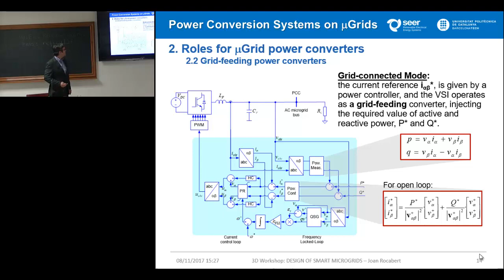Later we get the grid forming ones. The grid forming converters are voltage control systems that impose a frequency and an amplitude, and from that frequency and amplitude generate a sinusoidal by mathematical equation. From that, the equivalent representation is a voltage source in series with an impedance.